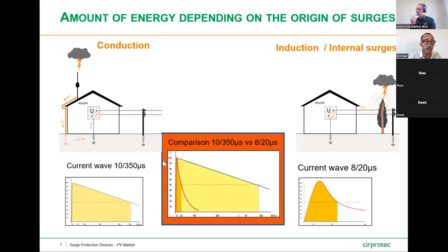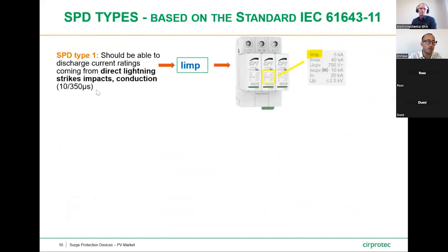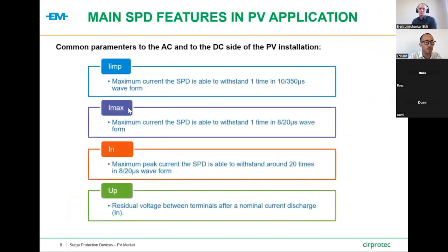The key here is to get this overlap between both current waveforms to see, and at the end, the aim behind these waveforms is to see that the worst energy generating scenario is the one belonging to direct lightning strike impacts in our installations where we do have a lightning rod in place. So then, with the slides we've shared with you with the different types of SPDs, this is why the SPD type 1, that should be able to discharge current ratings coming from direct lightning strike impacts, the scenario of conduction with the waveform 10/350, should declare the Iimp, the parameter referring to the waveform of conduction according to the standard.